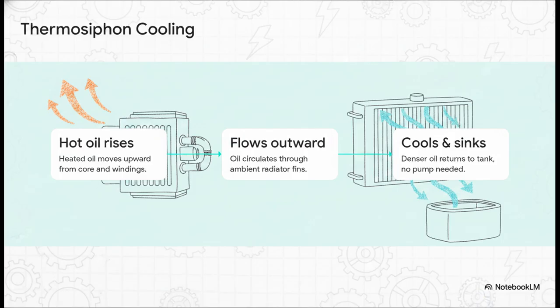The most obvious features on an oil-immersed unit are those big detachable radiators, and they run on this brilliantly simple physics principle called thermosiphon cooling. Basically, hot oil naturally rises from the core and windings, flows outward into the radiator fins where the outside air cools it down, and then that denser, cooler oil just naturally sinks right back into the tank. It's a continuous loop of removing heat, and it does all of this without a single mechanical pump that could break down on you. Pretty elegant, right?